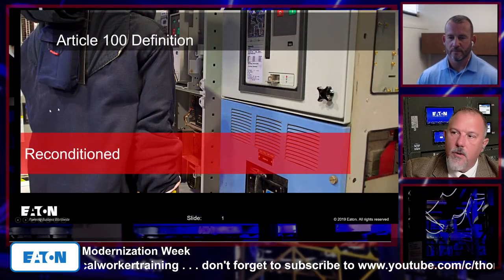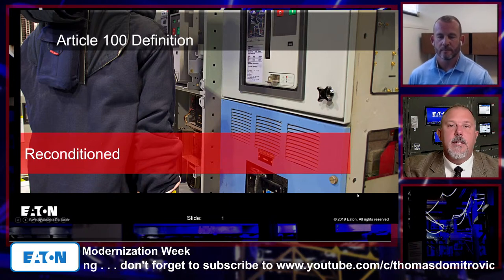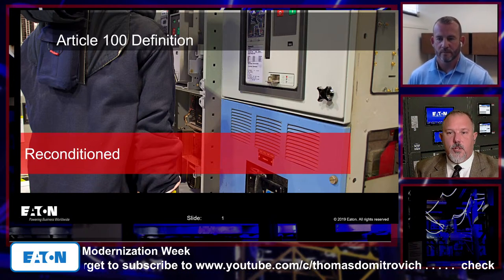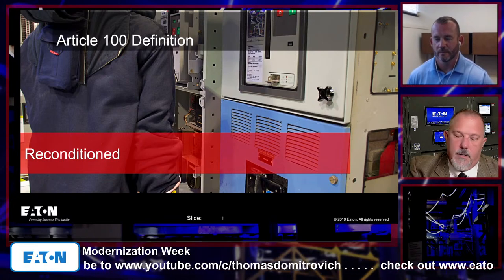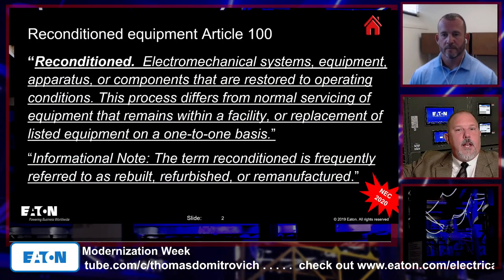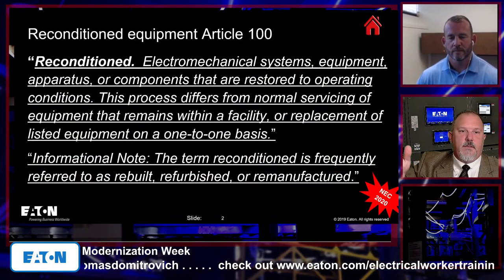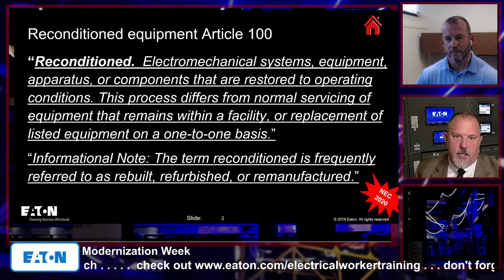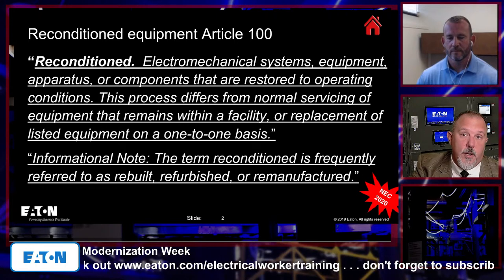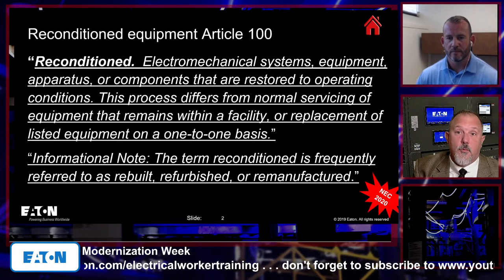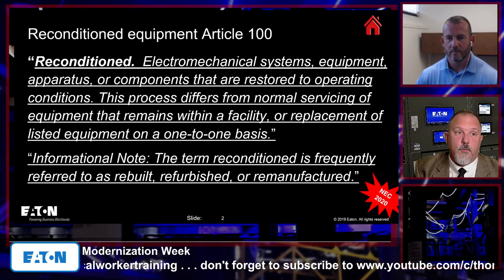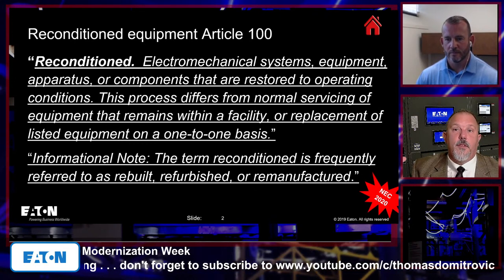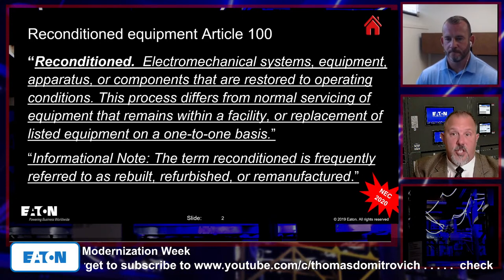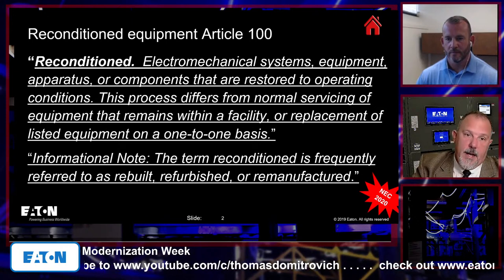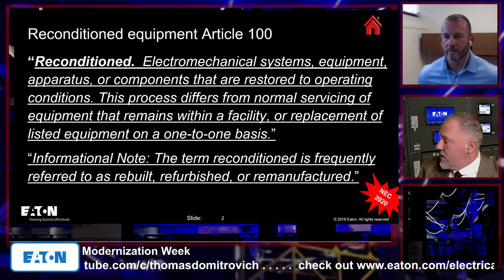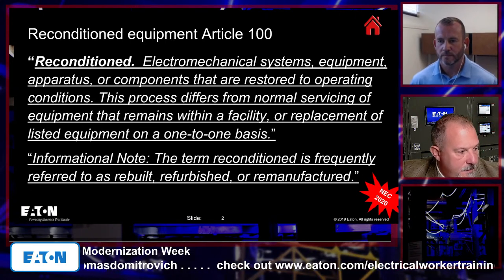So reconditioning—there's an article with some new changes in the NEC regarding reconditioning. The definition says if you restore a piece of equipment from a non-functioning to an operating condition, that's not normal servicing, and what you're doing on medium voltage equipment is not normal servicing. You're redoing a lot inside that equipment. It might not be with the low voltage assembly itself, it might just be with the circuit breaker.